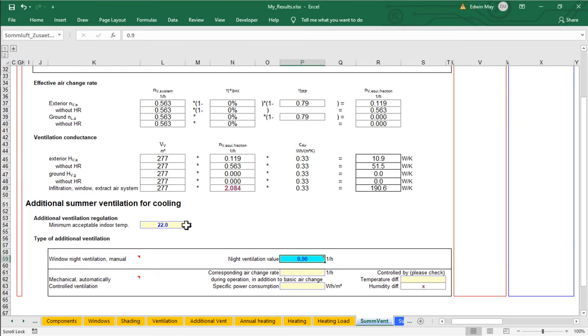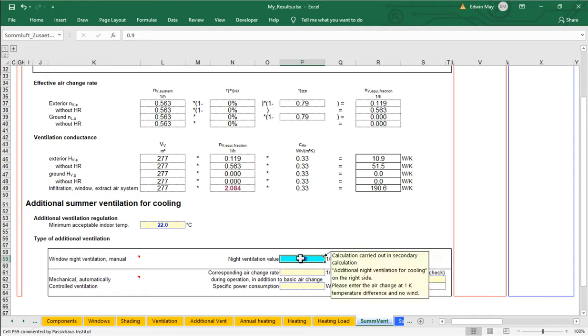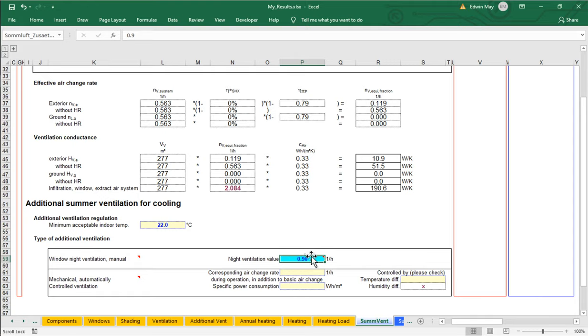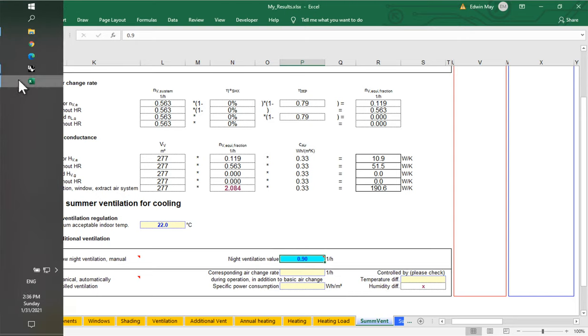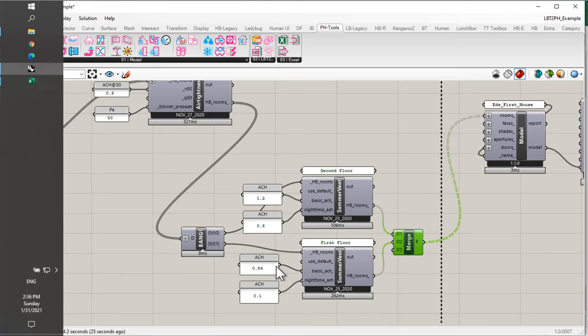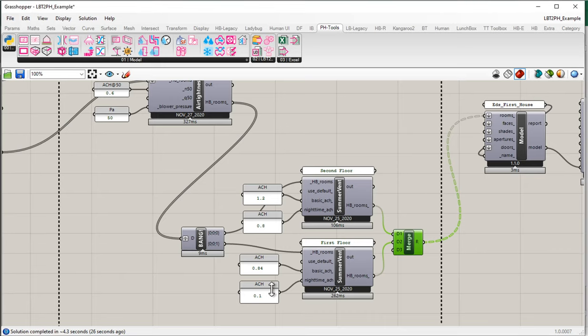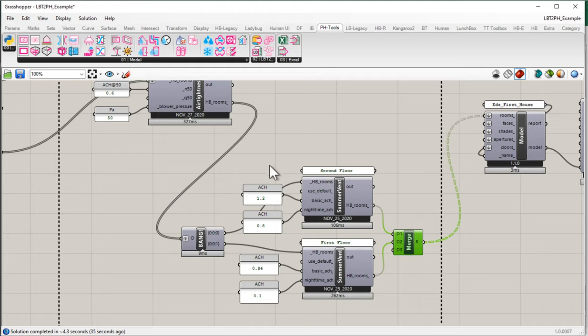It allows us to break apart the zones, assign individual elements to the zones, those get added back together. And then in the PHPP, those get summed up for the total building air change rate. So 0.9 gets entered here, 0.8 plus 0.1 gives us 0.9. We can absolutely work with this tool in this manner. That would be fine.